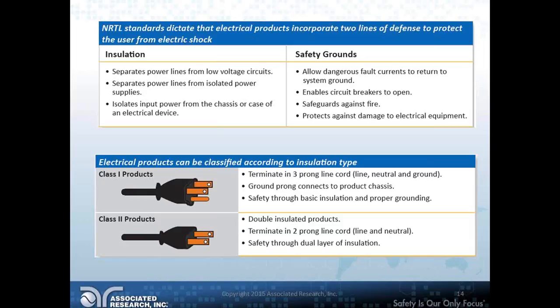They dictate that electrical products incorporate two lines of defense to protect the user from electrical shock: insulation and safety grounds. There's also a difference between Class 1 and Class 2 products, which ties into the insulation part as well. Insulation separates power lines from low voltage circuits, separates power lines from isolated power supplies, and isolates input power from the chassis or case of an electrical device. Thank God, since we're touching the chassis, we obviously want that isolated because we don't want an energized case. You saw what happened to Abe Lincoln in the previous slide - it wasn't a good story for him, it wasn't a good ending.